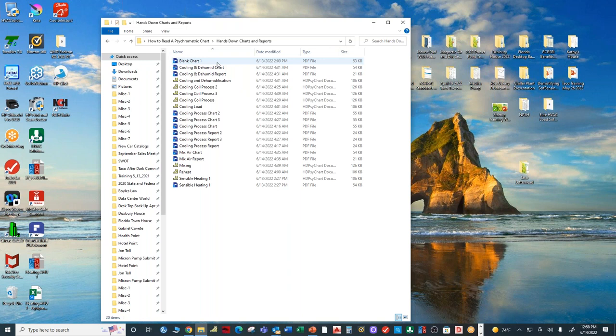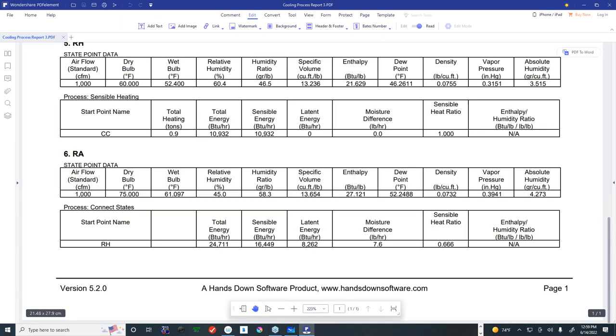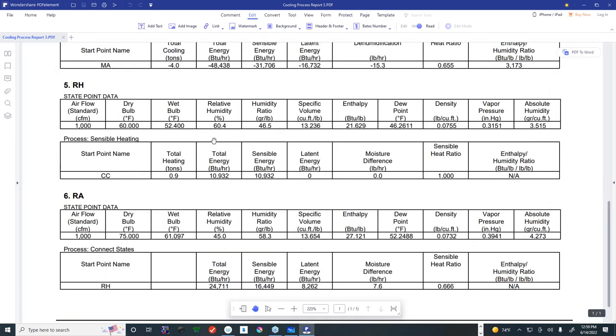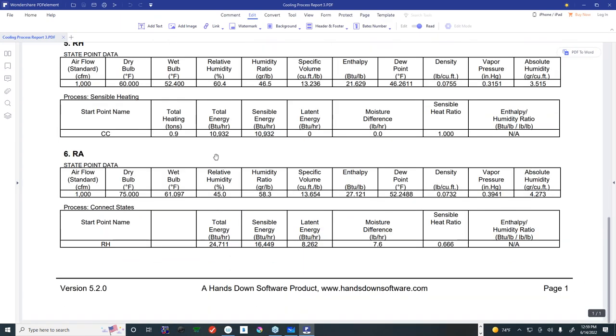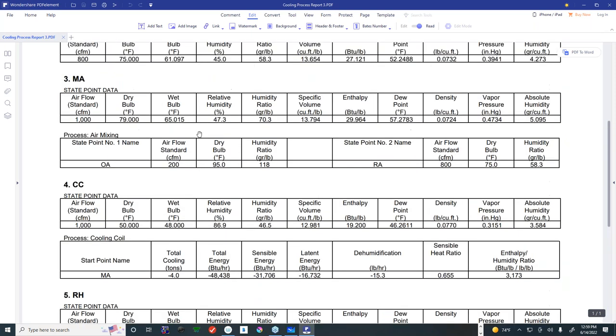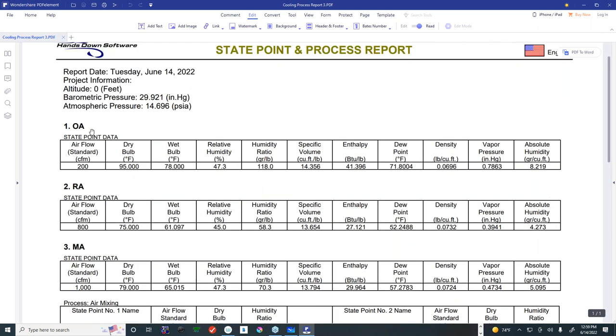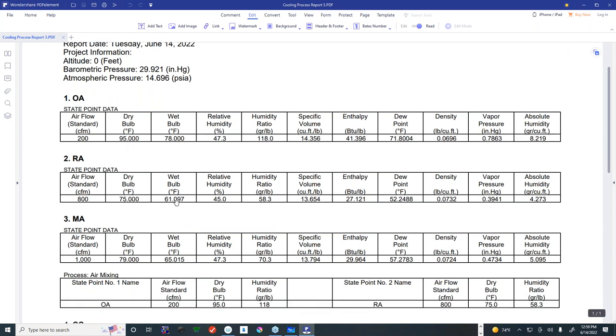So we wanted the cooling process and I wanted it in the report format. Here it is here. Ta-da, there it is. And so if you'll notice, these are all the points that we just plotted. There's the outside air, 95 and 78. There's the return air, 75 and 45% relative humidity. I'm going to highlight these things here so we don't lose track of them.